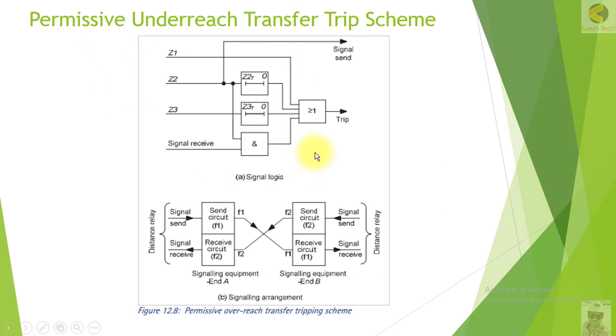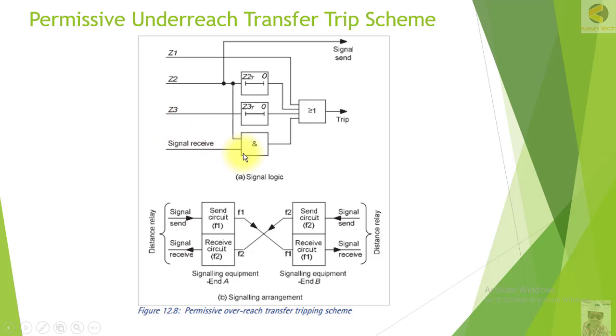Another option is that instead of using Z1B you can also use Zone 2, which can be set independently. Zone 2 can also be used in this scheme. If there is a fault in Zone 2, the signal is sent, and if the signal is received and the relay is also picked up in Zone 2 in the forward direction, then the relay will trip immediately.